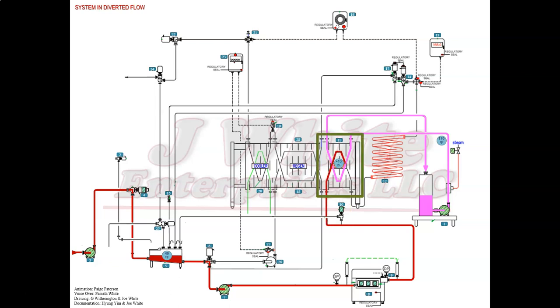The heater section heats the product 10 to 12 degrees per pass. That is why it runs in diverted flow for 8 to 10 minutes to reach forward flow temperature. Once in forward flow, the regenerator preheats the product allowing the heater section to supply the last 10 to 12 degrees.